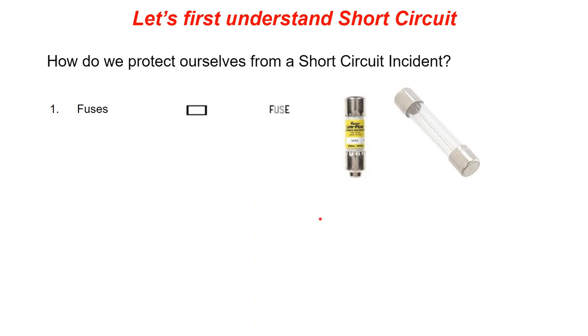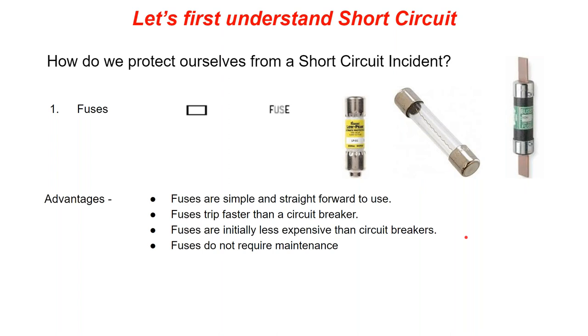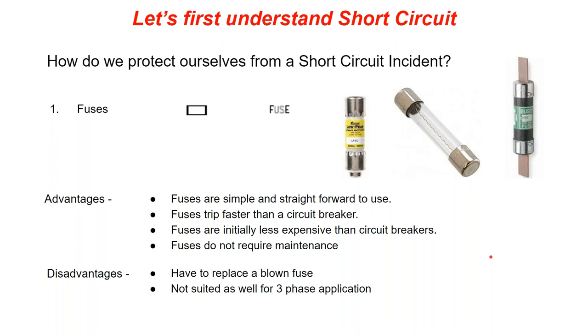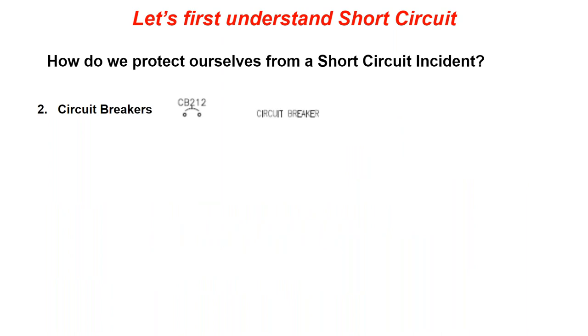Fuses are used to break the circuit quickly. Advantages: they're simple, trip very fast, inexpensive, and require no maintenance. The downside is that you have to replace a blown fuse with the exact same type, which can take time in a factory. Also, in a three-phase application, if one fuse blows, the other two phases could still be live.